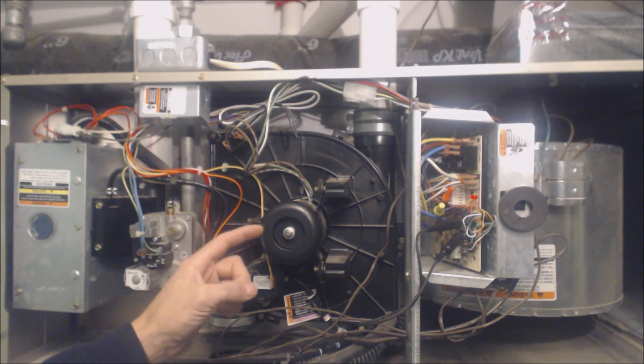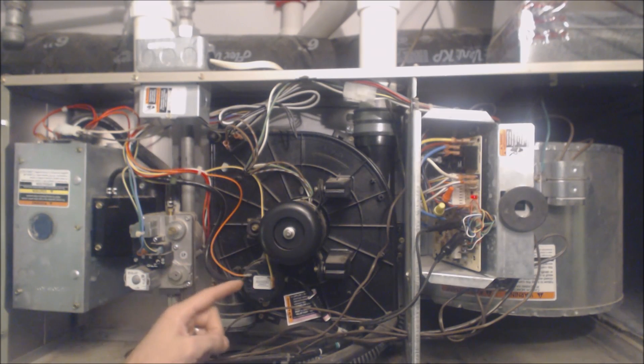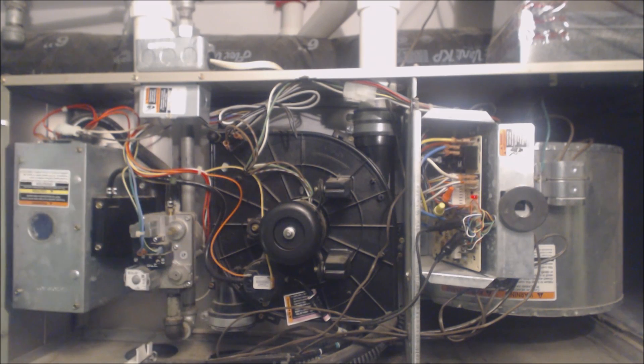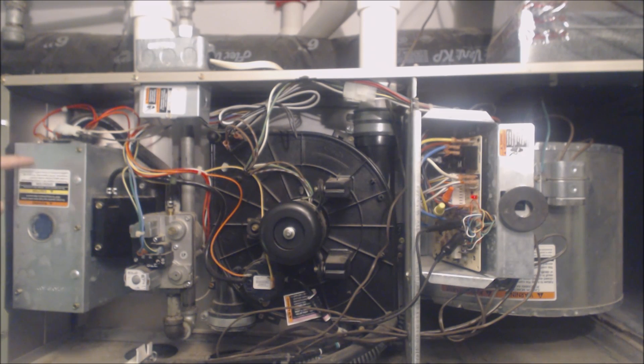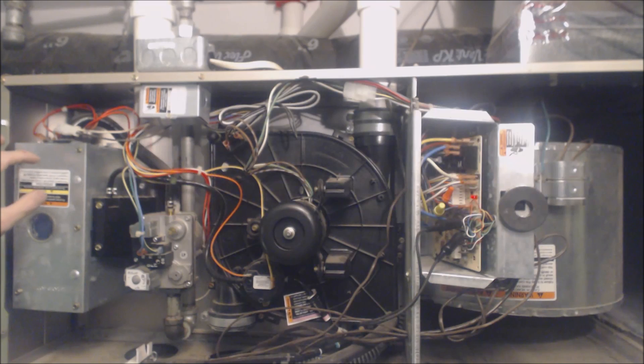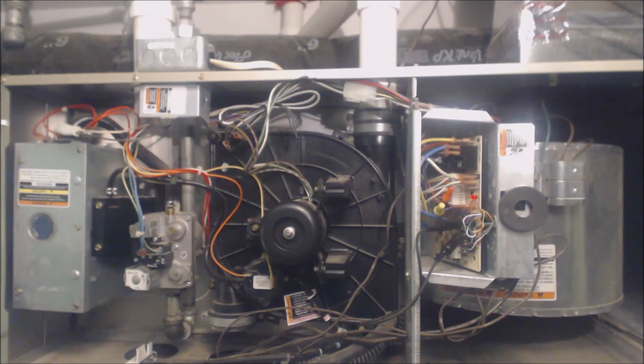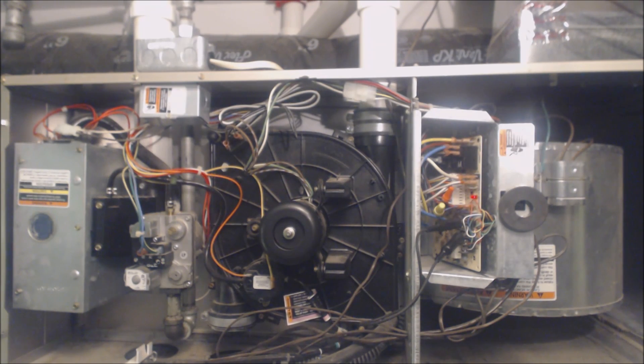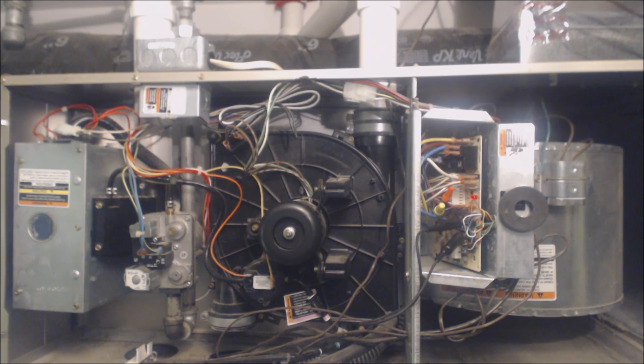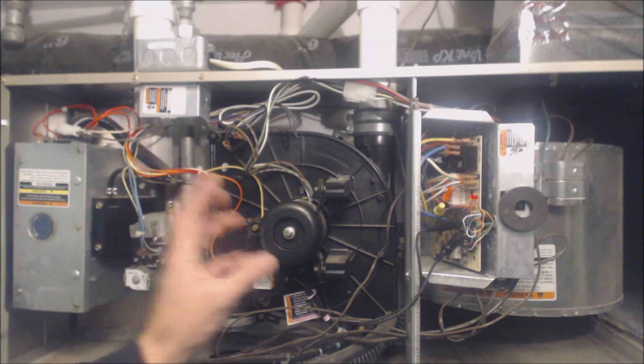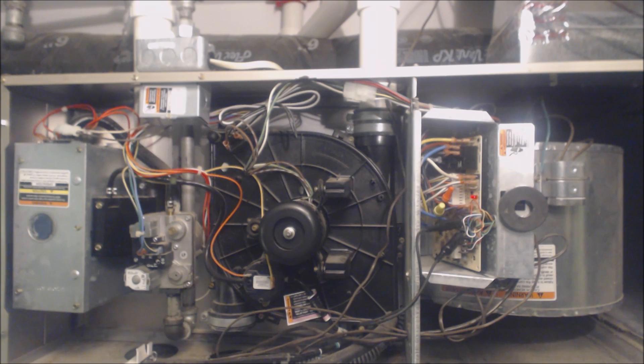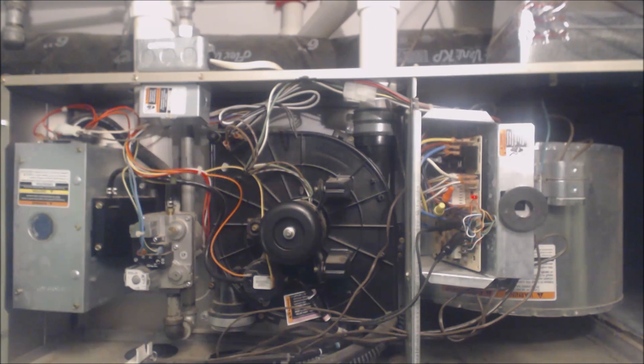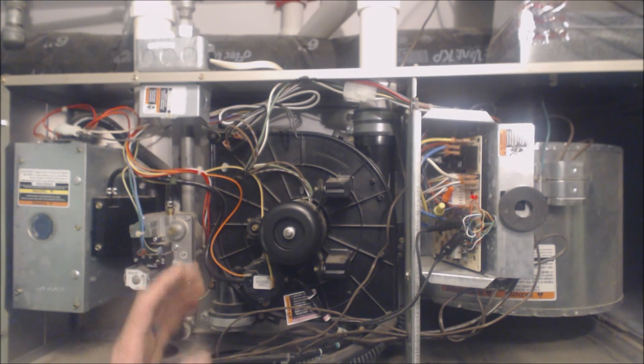Or say the inducer motor turned on, the pressure switch closed, the hot surface igniter did not turn cherry red. So then you know, hey, maybe it's the hot surface igniter is the problem. I'm going to show you how to diagnose each of those in another video. I'll show you each step of the sequence of operation, but that's how it works.